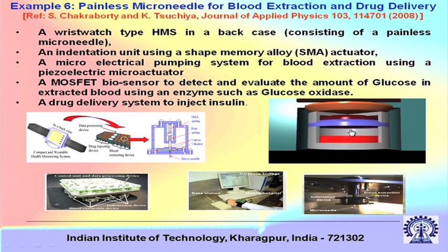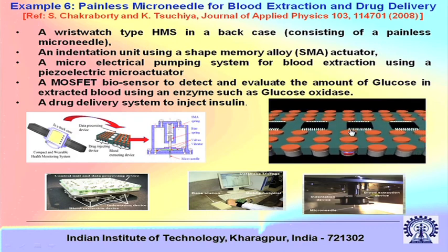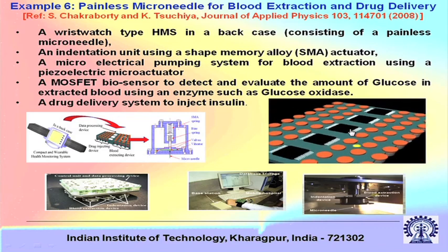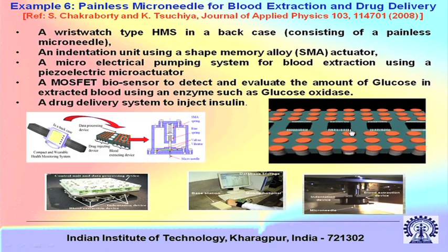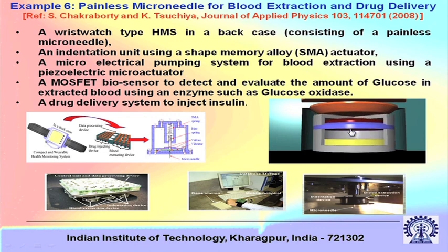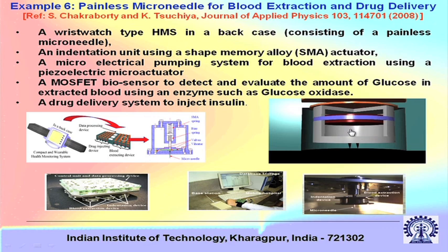There is a micro electrical pumping system for blood extraction using a piezoelectric micro actuator — basically a blood extraction system designed based on a female mosquito's blood sampling mechanism. Then there is a MOSFET-based biosensor to detect and evaluate the amount of glucose in the extracted blood using an enzyme such as glucose oxidase. When the device senses the amount of glucose in the blood sample, there is a delivery of the necessary amount of insulin based on the glucose level at that particular instant of time.